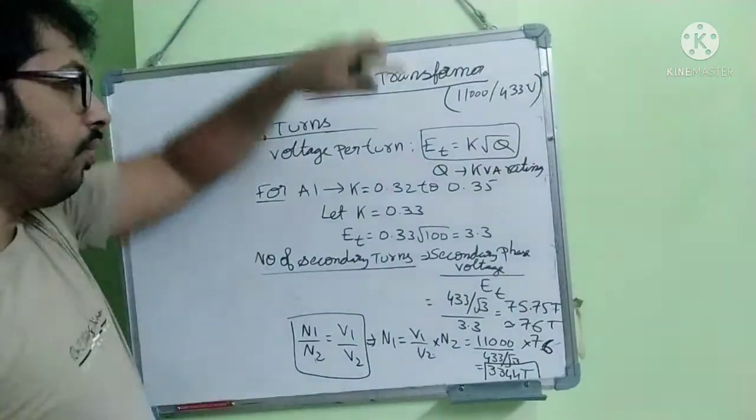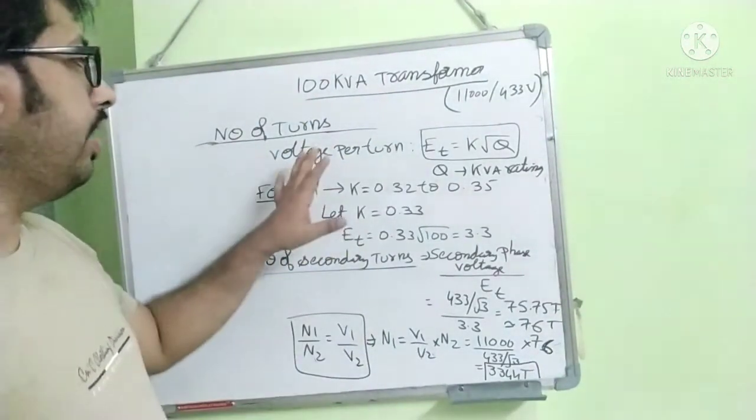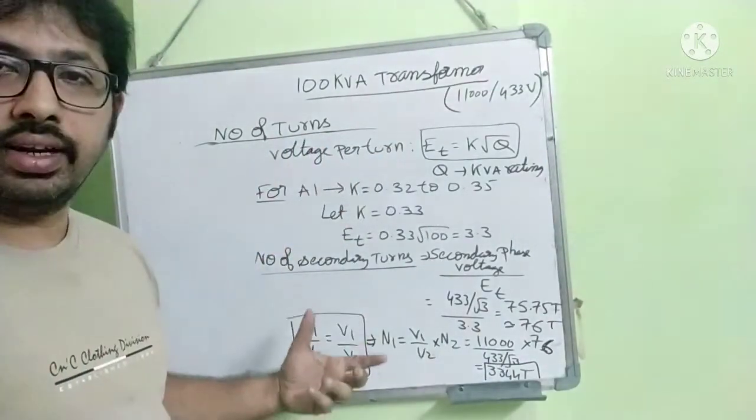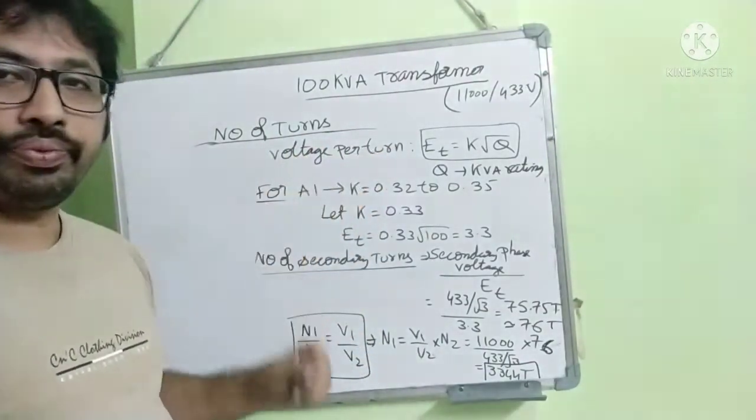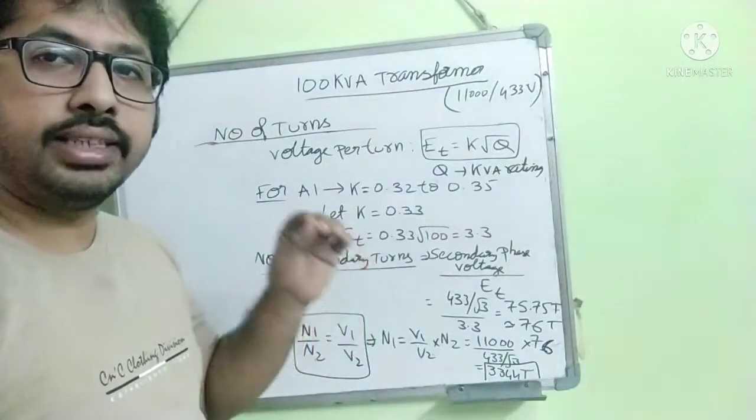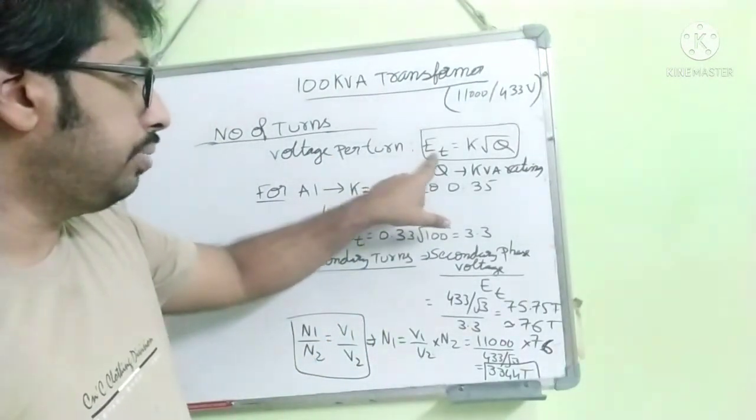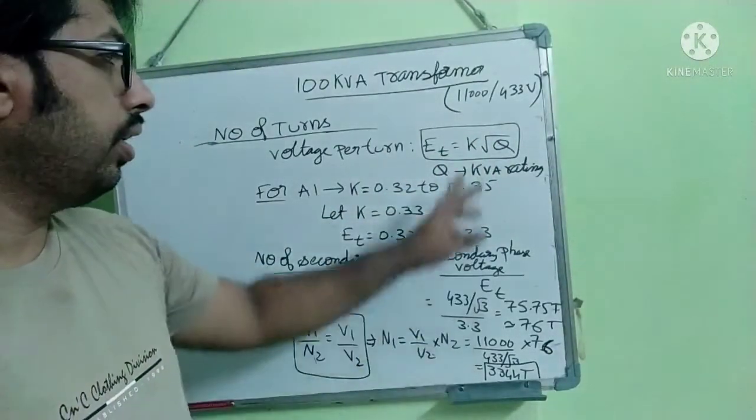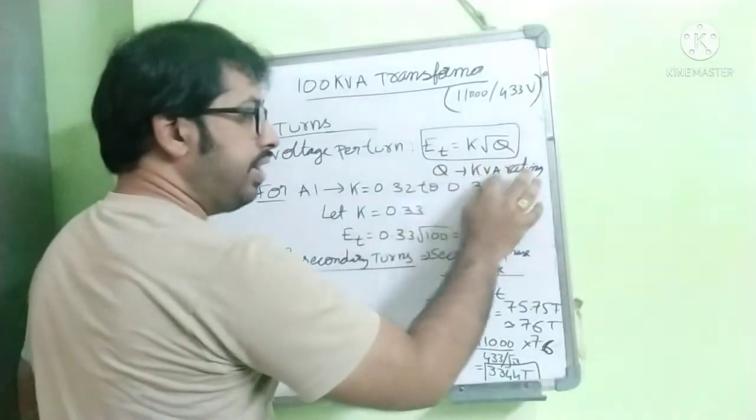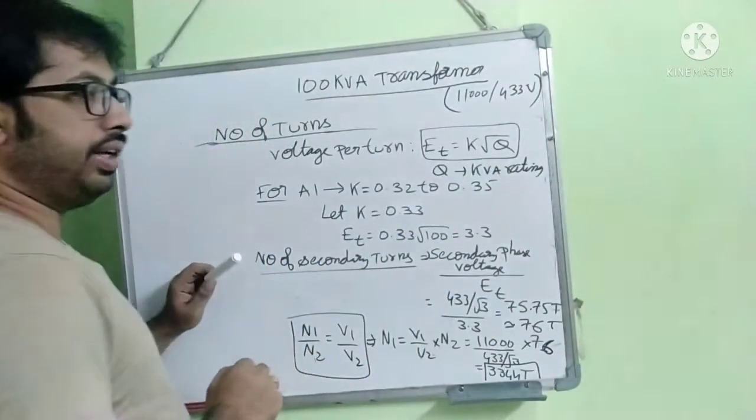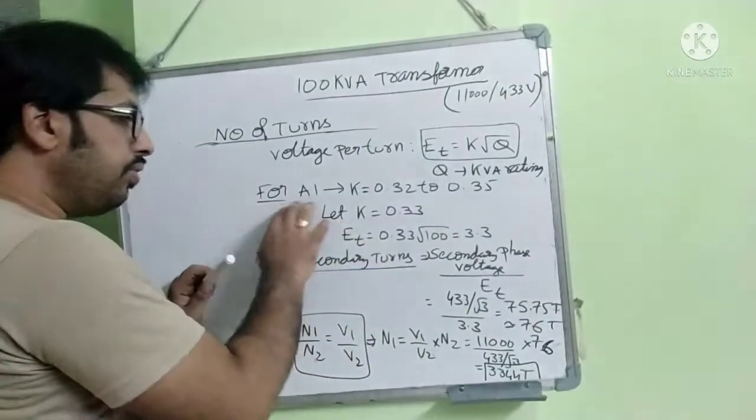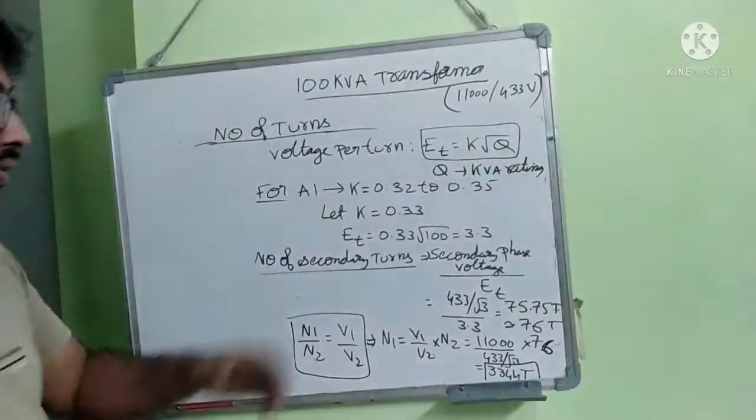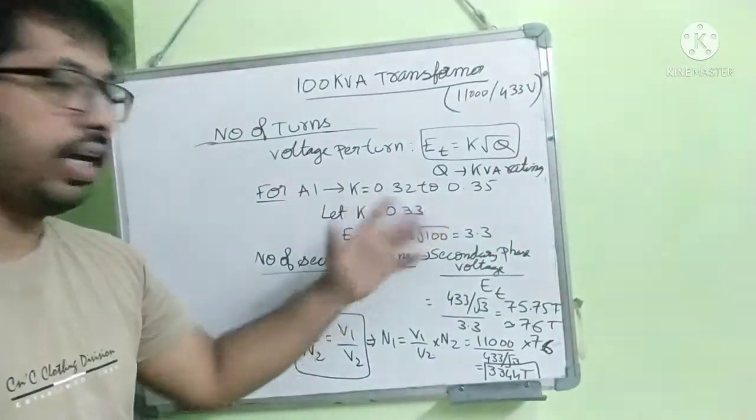To find number of turns, very important is to find voltage per turn. If you get this then easy to calculate. Voltage per turn has a formula. Voltage per turn is K under root Q, where Q is a kVA rating. And K value for aluminum winding is 0.32 to 0.35. In between these two values we should take the K value.